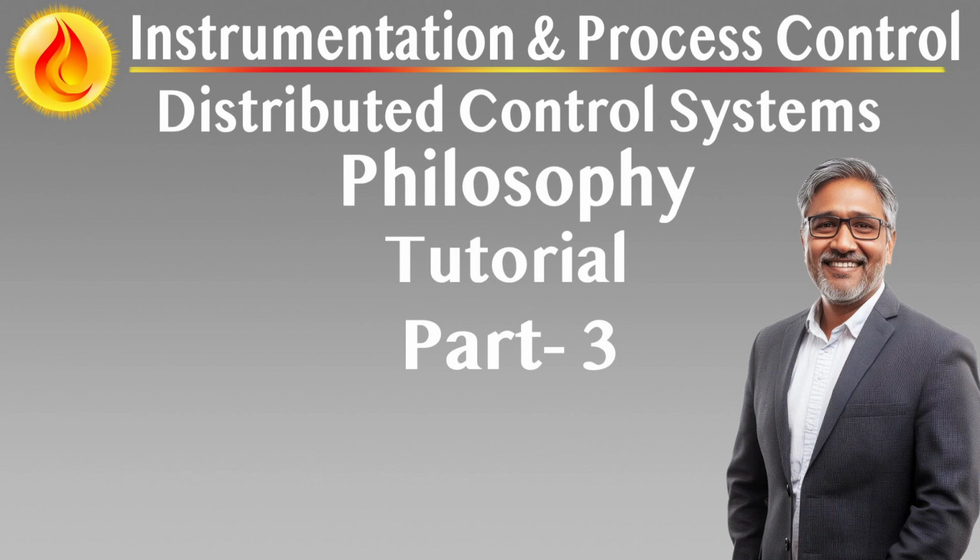Lifecycle maintenance integration. The FGS must interface with the CMMS, e.g. SAP PM, Maximo, to trigger maintenance work orders based on diagnostics, proof test results, and performance degradation trends. Modern fire and gas system design must not only detect hazards quickly, but also manage data, diagnostics, and decisions intelligently. These guidelines ensure a robust, transparent, and operator focused implementation that transforms the FGS from a passive alarm system into a proactive, predictive safety infrastructure.